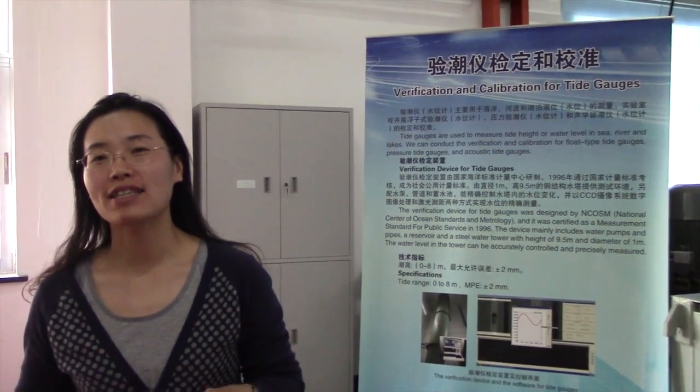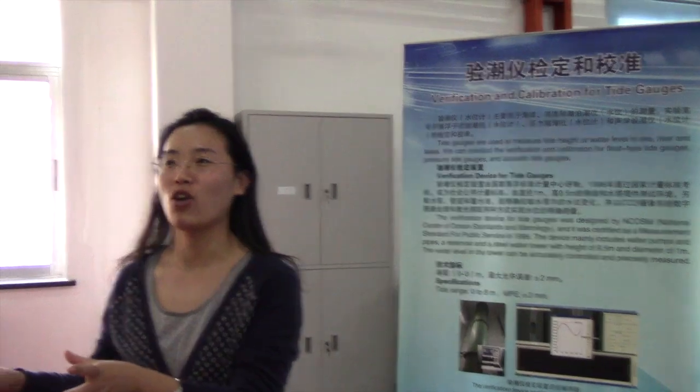In this lab, we calibrate tide gauges. Tide gauges are used to measure water level in the sea, rivers, and lakes. The main part of the calibration device is this steel water tower, which has a diameter of 1 meter and is 9.5 meters high. The water level in the tower can be accurately controlled and measured precisely. The measuring range is from 0 to 8 meters, with an MPE of ±2 millimeters.